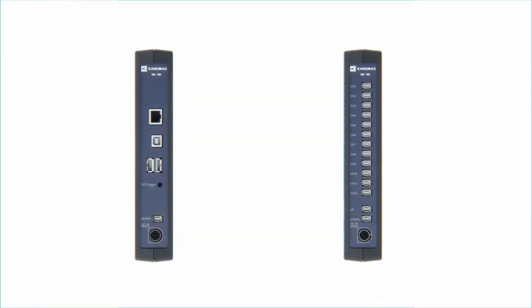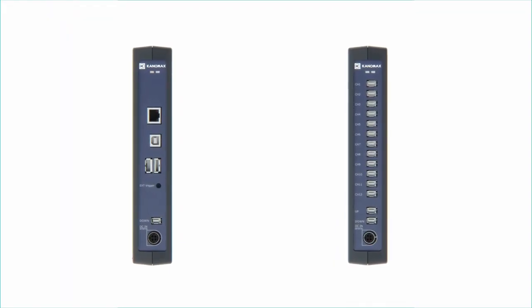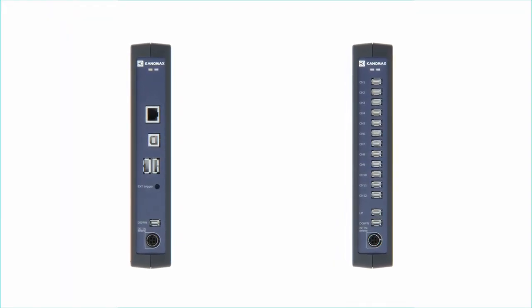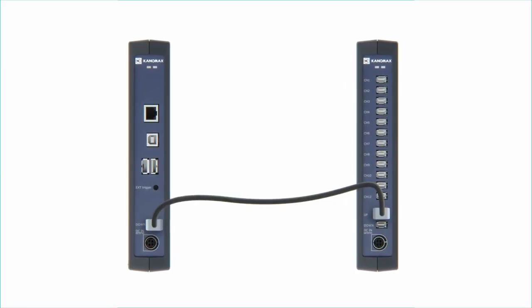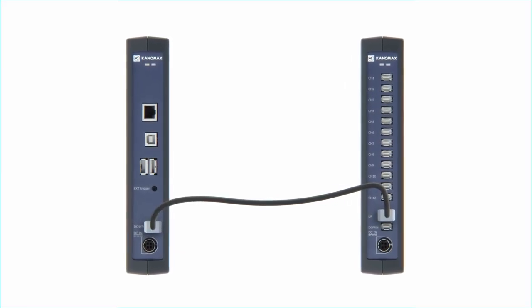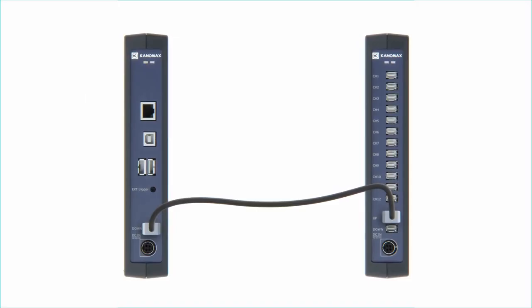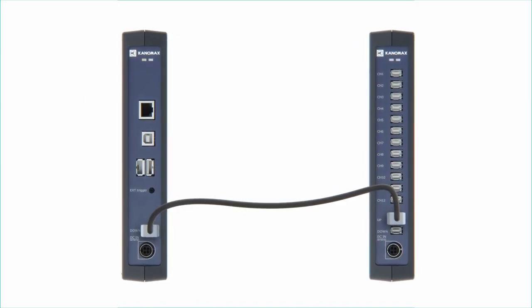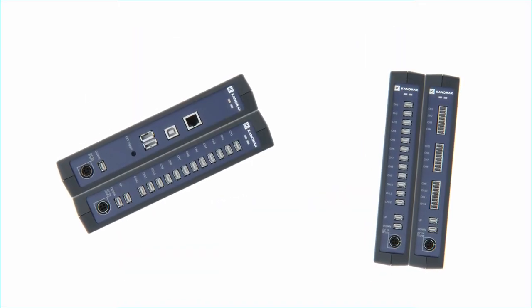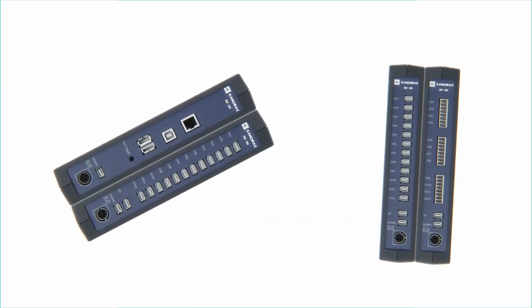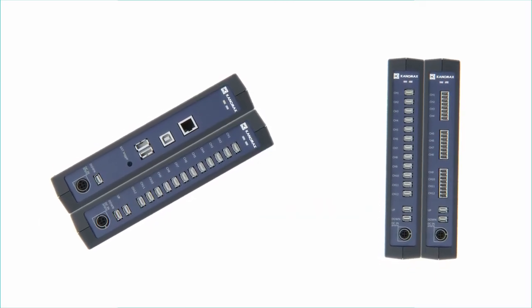The second and third methods are only possible on the 1590 model. Linking can be achieved by using the optionally available standard cable. This configuration doesn't require that the units be a connected unit block, allowing the units to be positioned freely from one another if needed. And the third method utilizes both linking methods.